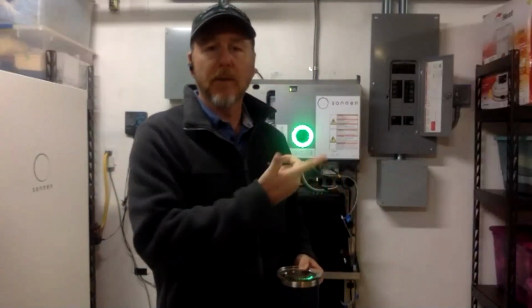Now, there aren't too many single ESS units that have enough oomph to start something like an air conditioner. A 3-ton air conditioner averages anywhere between 65 and 80 amps of startup. So one unit, one of anything, probably won't start it. You're going to have to double up or get a soft start kit, so you add a soft start element in there. It's about $250, so it's an adder, but it absorbs some of the surge from these larger loads so that you don't have to pull so much off of these.